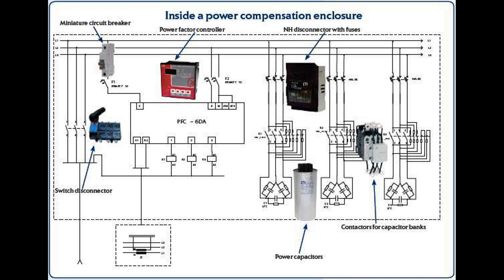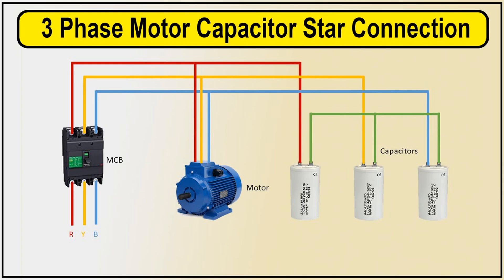Harmonic distortion can have detrimental effects on sensitive equipment such as transformers, motors, and electronic devices. Detuned capacitors help protect equipment by reducing harmonic distortion and preventing excessive heating, insulation breakdown, and premature failure. Detuned capacitors require careful sizing and placement in the electrical system to effectively mitigate harmonic distortion. They are typically installed in parallel with the load or in a dedicated harmonic filter bank to ensure optimal performance.